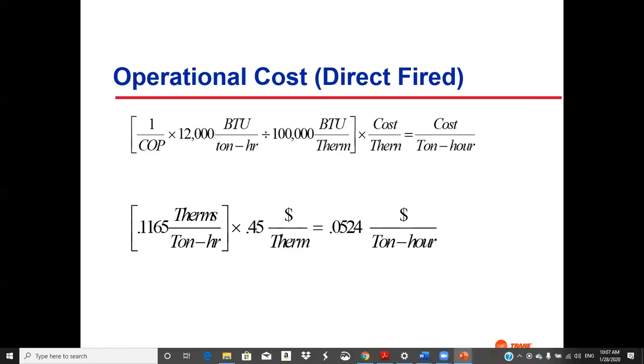So this was the therms per ton hour for the direct fired from our previous analysis. It's 0.1165 therms of gas. I don't do math in my head very well anymore. Anyway, that's the therms per ton hour times $0.45 per therm, so it's $0.0524 per ton hour.